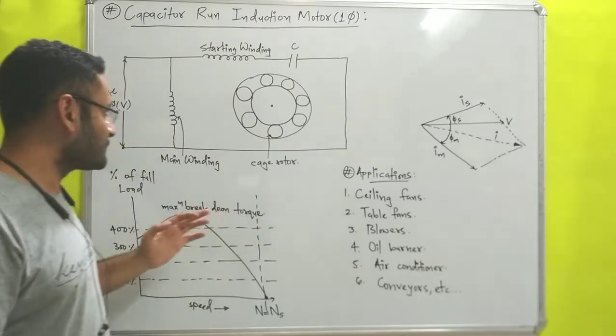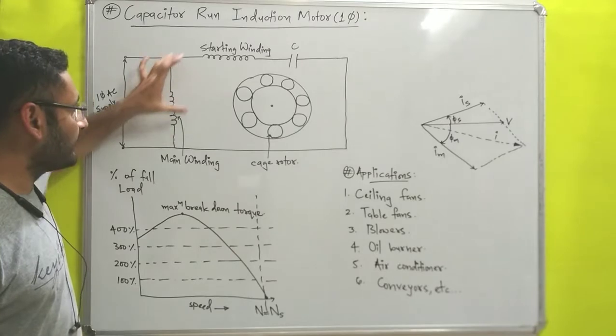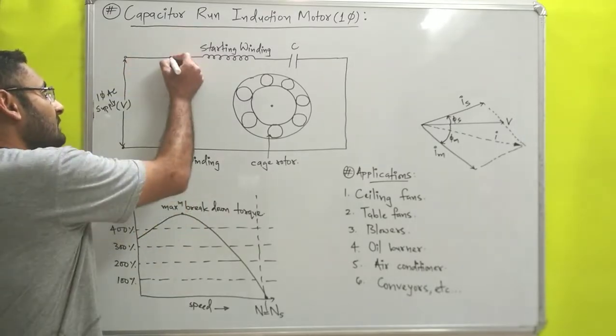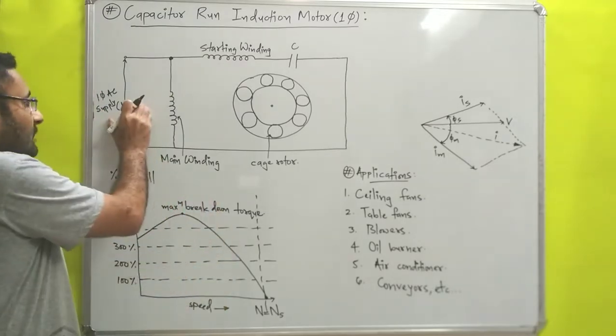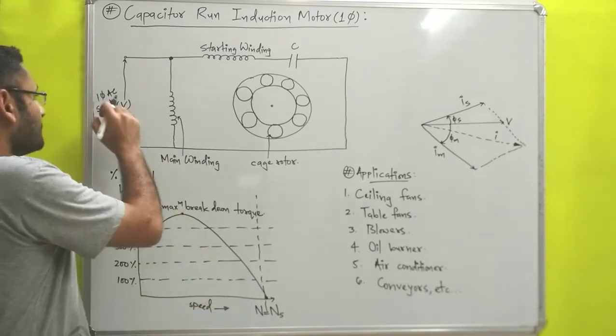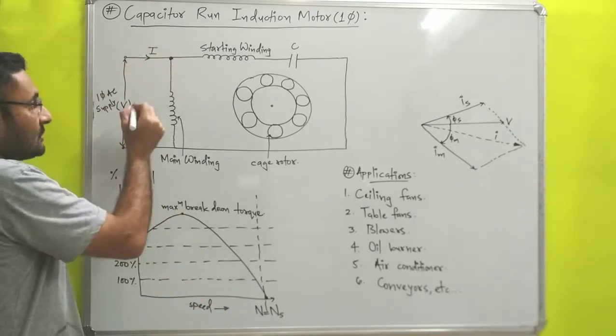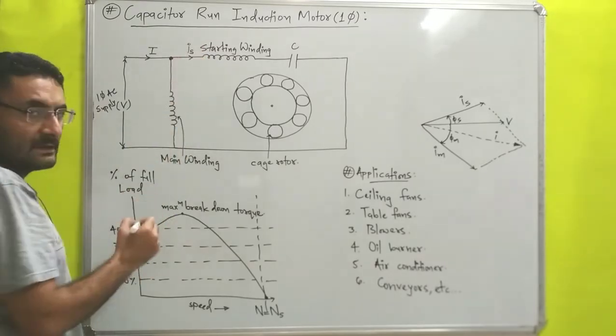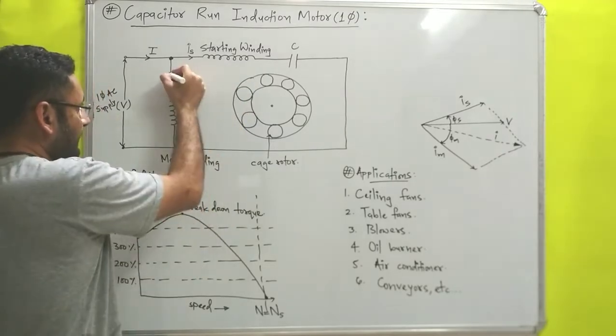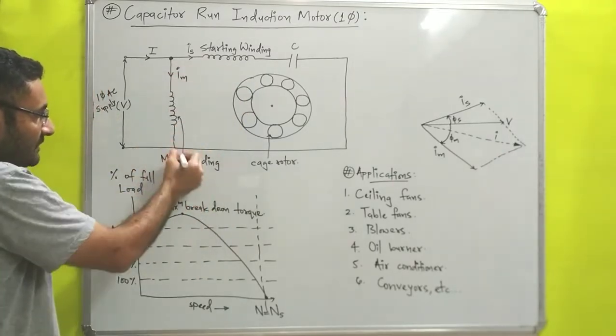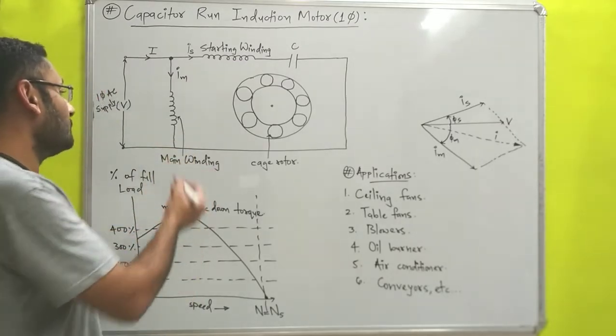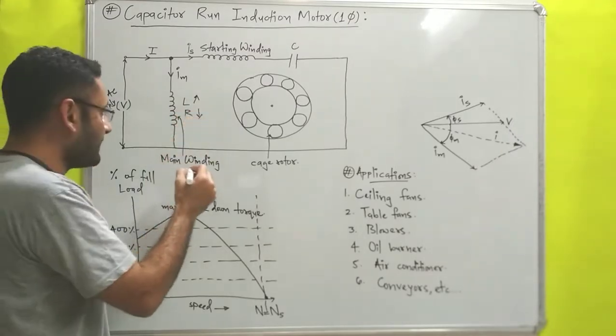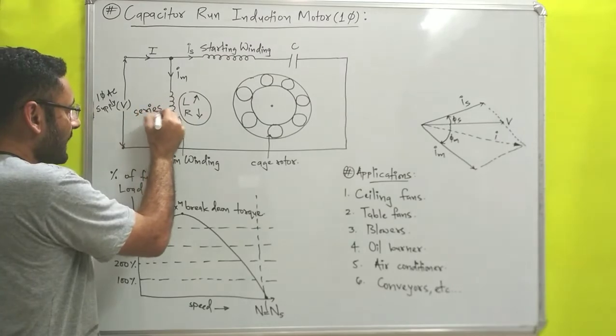Now we will discuss the construction. It has one main winding and one starting winding. Both the main winding and starting winding are connected in parallel with each other across a single phase AC supply voltage V. From the voltage source, current I flows and at the junction it divides: Is flows through the starting winding and Im flows through the main winding. The main winding is designed to have high inductance and low resistance, making it a series LR circuit.